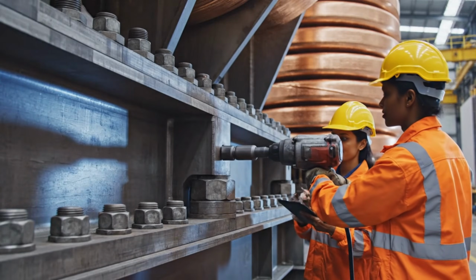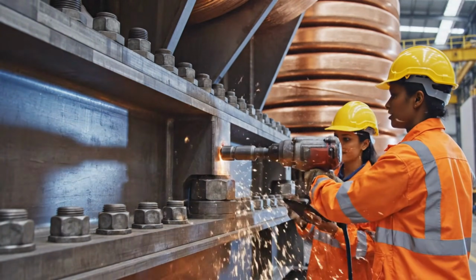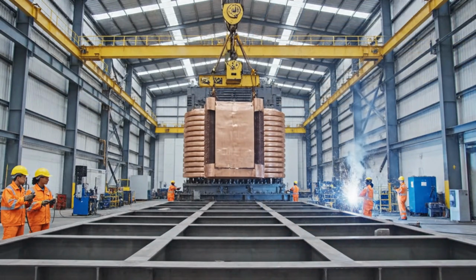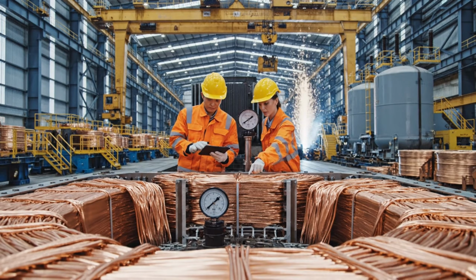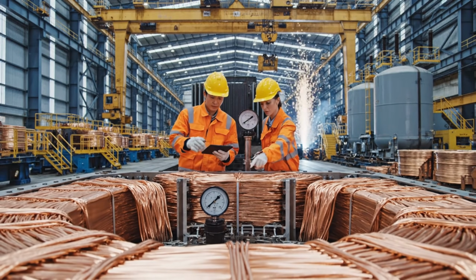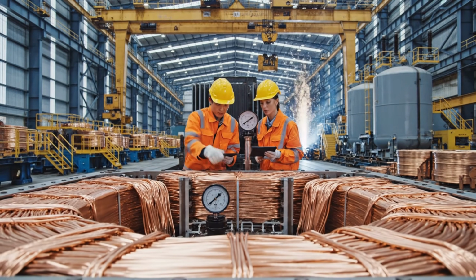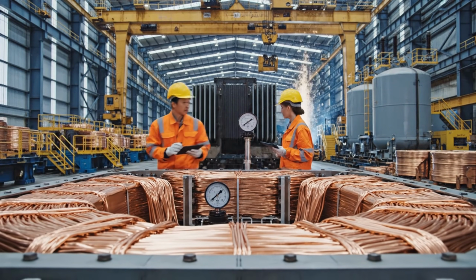The core frame, central to the transformer's function, is systematically tightened with high-torque impact wrenches. The resistance readings are within tolerance on phase C. Confirmed. The insulation looks good too. Let's sign off on the final report.